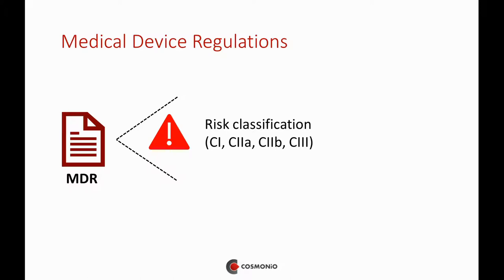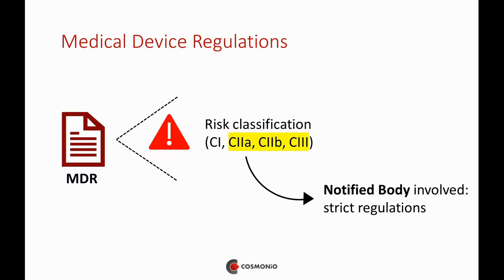Moving from this American example to European legislation, the regulatory hurdles for adaptive algorithms are quite similar. The European Medical Device Regulation, the MDR, is a new set of regulations that governs the production and distribution of medical devices in Europe, and compliance is mandatory for medical device companies that want to sell their products in the European marketplace, including software as a medical device. The MDR contains a risk classification framework that determines which conformity assessment procedures are applicable, and the higher the risk class indication, the more regulatory hurdles there are to take. For example, class 2A devices already require an assessment procedure performed by a third-party notified body, which goes hand in hand with strict regulations.